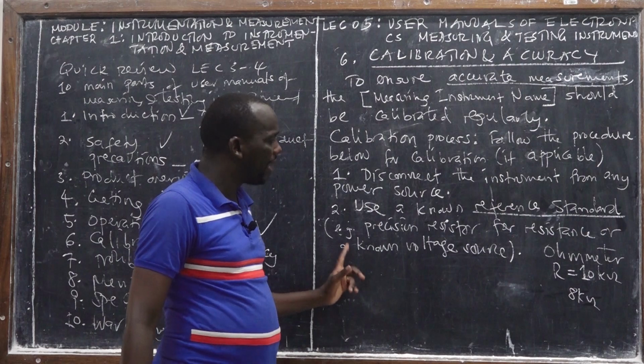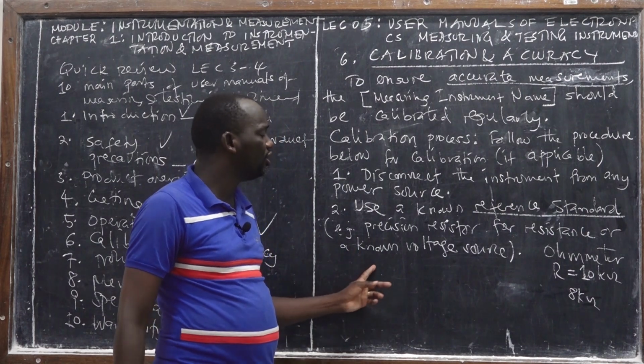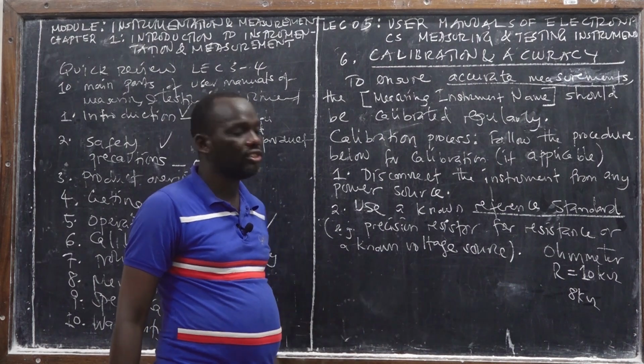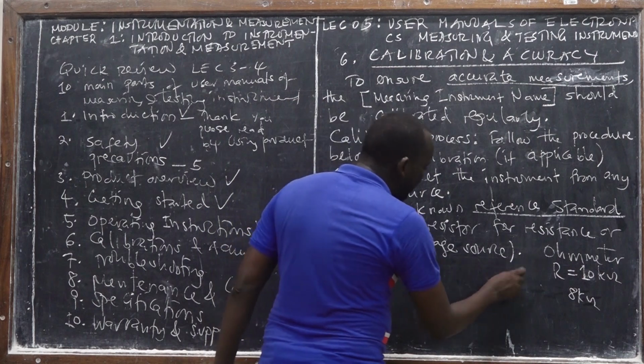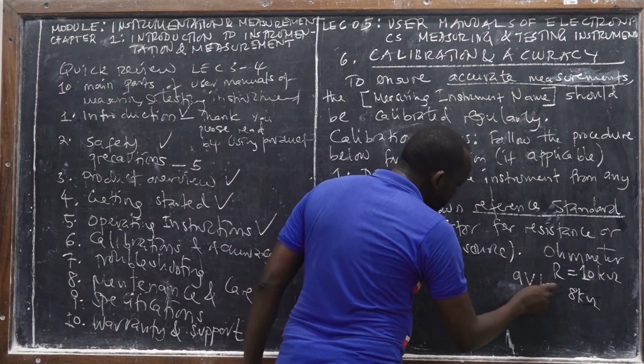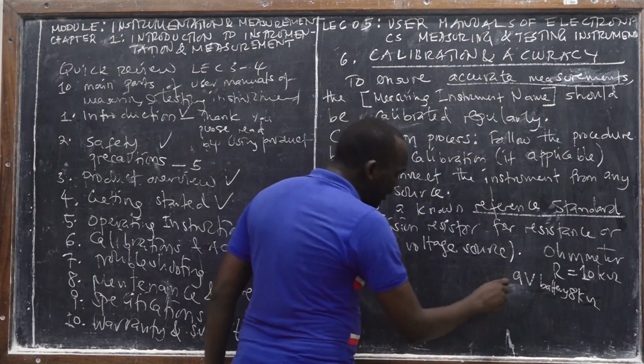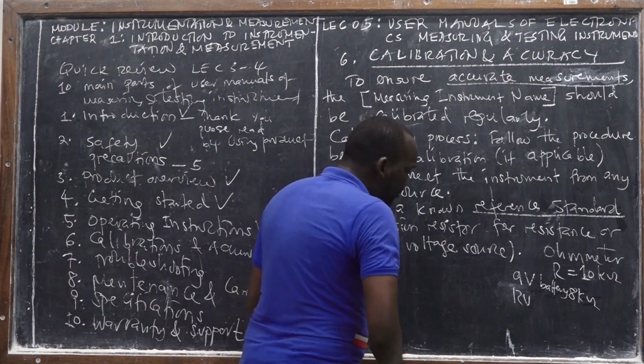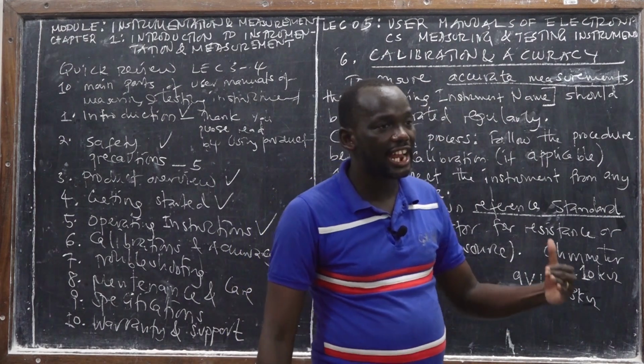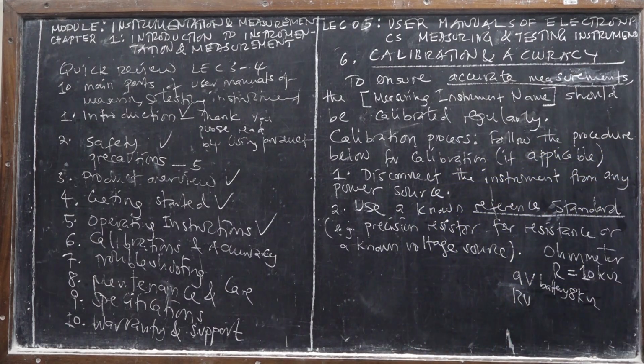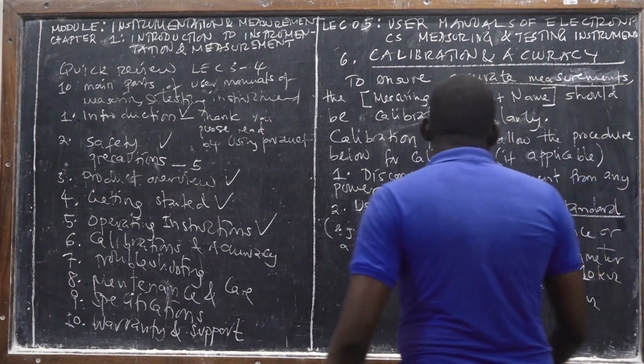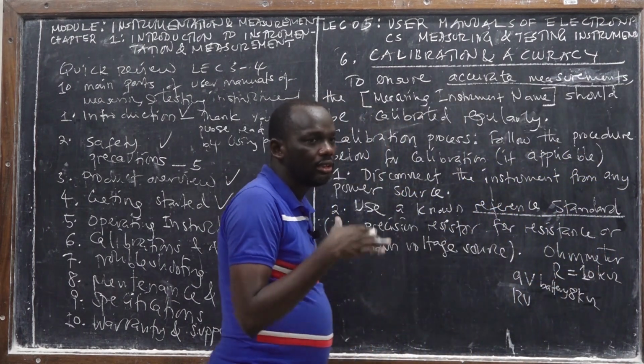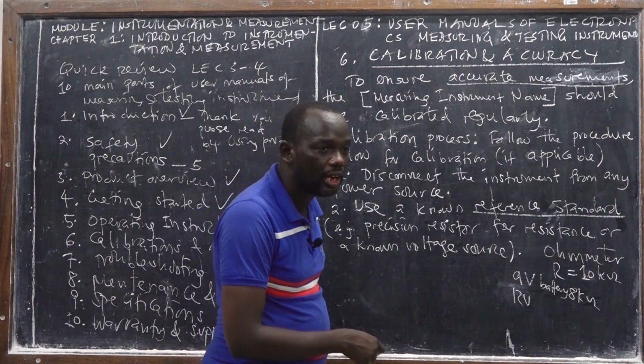Also, another way: if you want to calibrate a voltmeter, then you have to use a known voltage. For instance, a 9 volt battery, or a 12 volt car battery. You must find a source of voltage that is standard and known. Then you use that DC voltmeter to measure it. In case you find the reading is different from what you expected, then that instrument needs to be calibrated. But how did you know you are supposed to calibrate? Because you use the standard known physical quantity. Is it clear?